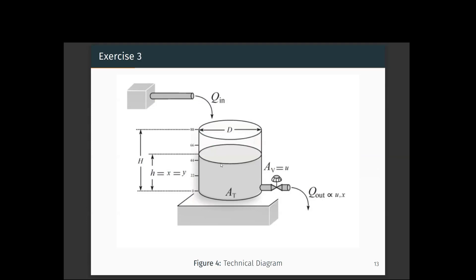There are two ways of controlling this water level, and for both we need a sensor to sense the level of the tank — like the float used in the first example. The sensor reading is sent to a controller. The controller can send an instruction to the inflow valve to control the inflow based on the desired set point. If the set point is 66 centimeters, the controller instructs the inflow valve to open more so that more water flows in and the set point is reached.